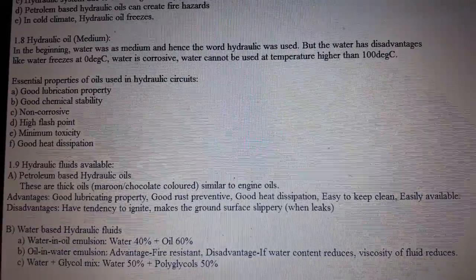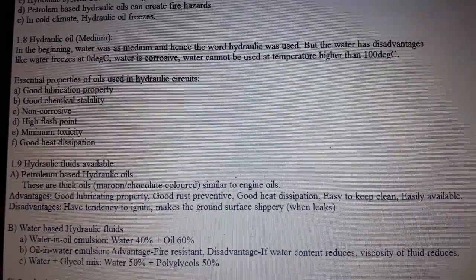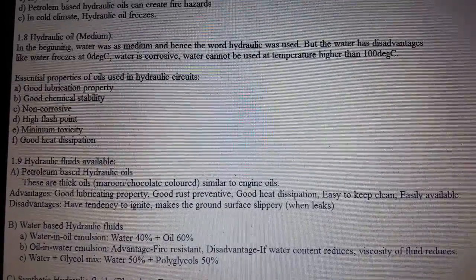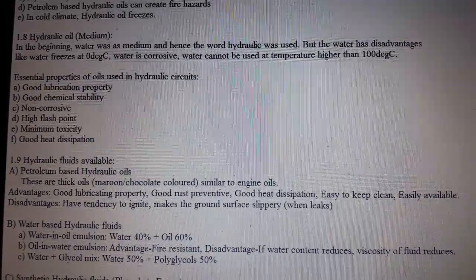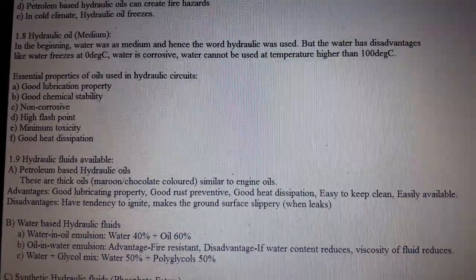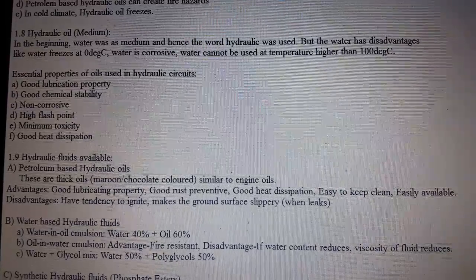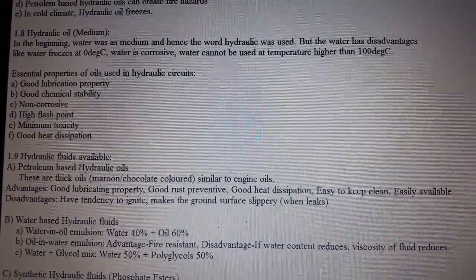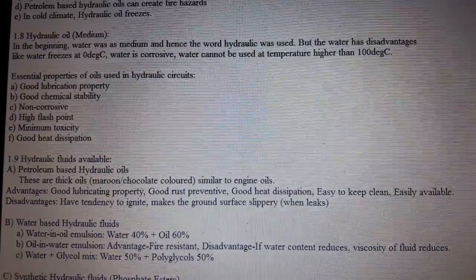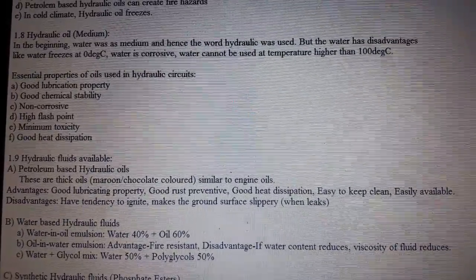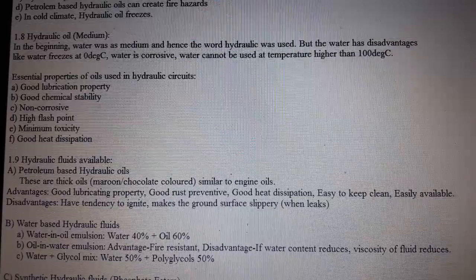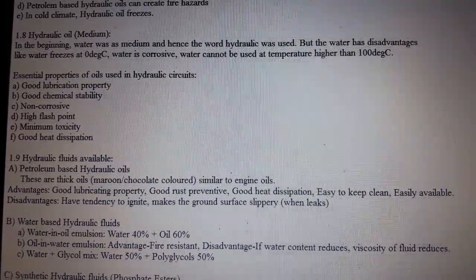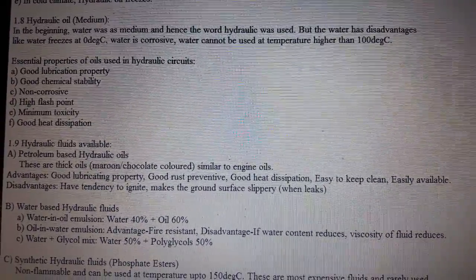1.9 Hydraulic fluids available. A. Petroleum-based hydraulic oil: these are thick oils, maroon or chocolate colored, similar to engine oil. Advantages: good lubricating property, good rust prevention, good heat dissipation, easy to keep clean, and easily available. Disadvantages: tendency to ignite and makes ground surfaces slippery when it leaks.